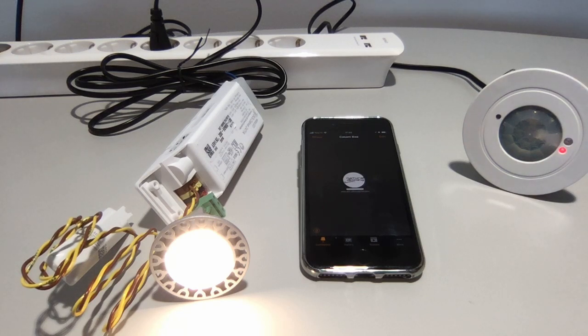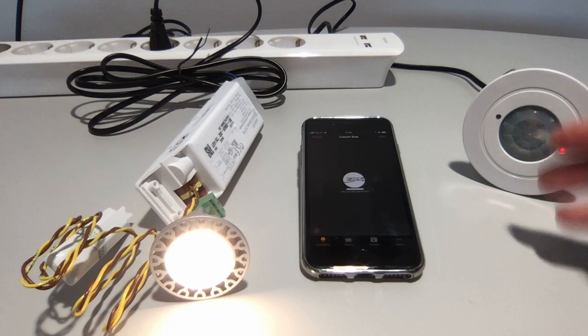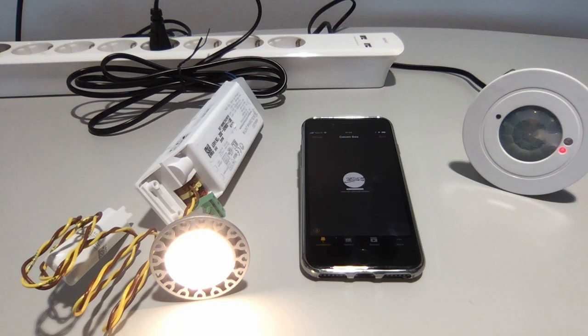I forget to turn the lights off. So what happens is, the presence sensor waits for absence. It then must wait for the 10 seconds linger time to pass, and it will then turn the lights out.